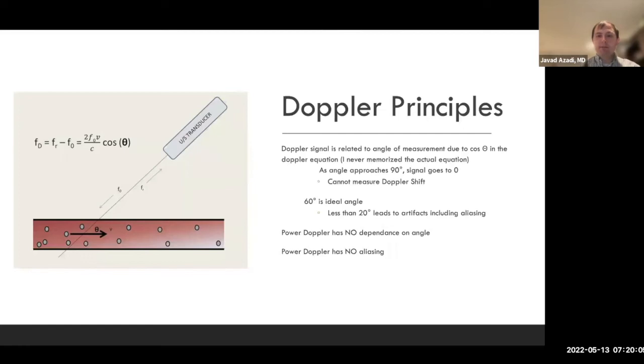For the Doppler principles, Doppler signal is related to the angle of measurement due to cosine theta in the Doppler equation, which is written here. I've never memorized that actual equation. I just understand that the angle is going to determine whether or not your velocity measurement is accurate. So if the angle is 90 degrees, which means it's perpendicular to the blood flow, the shift goes to 0, so it can't measure any Doppler shift. 60 degrees to blood flow is ideal. If you have an angle less than 20 degrees, it actually leads to artifacts, including aliasing.